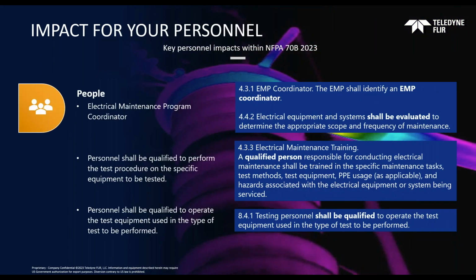And then moving into the people side. There's a role of electrical maintenance program coordinator that needs to be defined within your electrical maintenance plan. This person's responsibility, among other things, is the evaluation of the equipment to determine scope and frequency of maintenance. This could be an electrical or maintenance person, an electrical supervisor, or a plant manager. It just needs to be defined, and they're ultimately responsible for the content of the electrical maintenance program itself, having that role clearly defined in the new guidance as well.